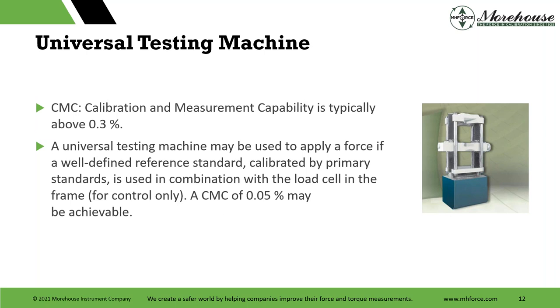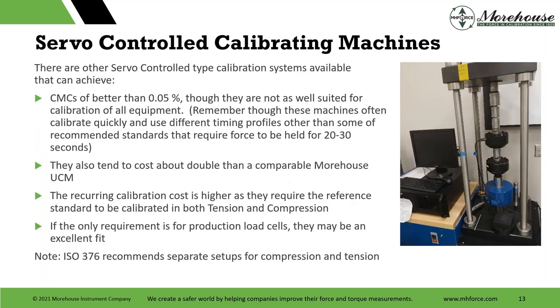So typically, this is that CYA, cover your butt, saying words like typically, because there are some that are better. They're typically above 0.3%. Some are much better. A universal testing machine may be used to apply a force. A well-defined reference standard calibrated by primary standards is used in combination with the load cell in the frame for control only. And then I made the note there that a CMC uncertainty parameter of 0.05 may be achievable.